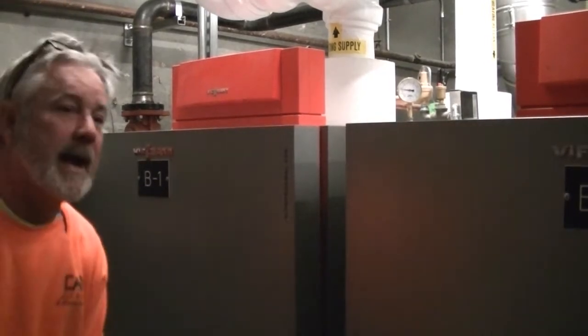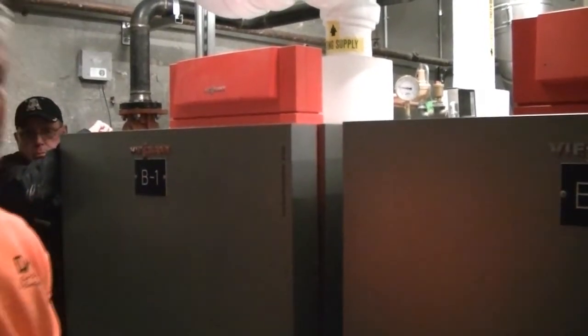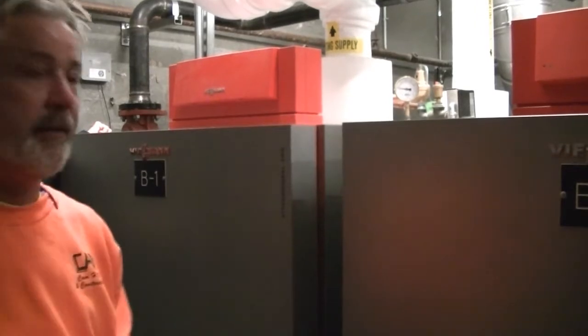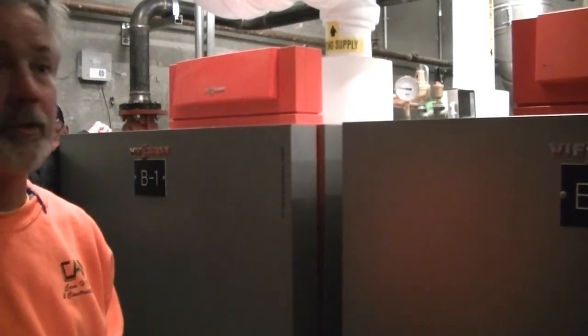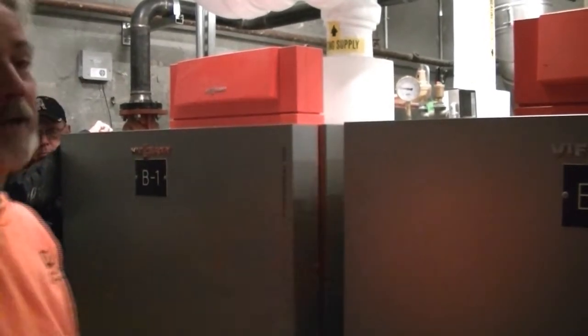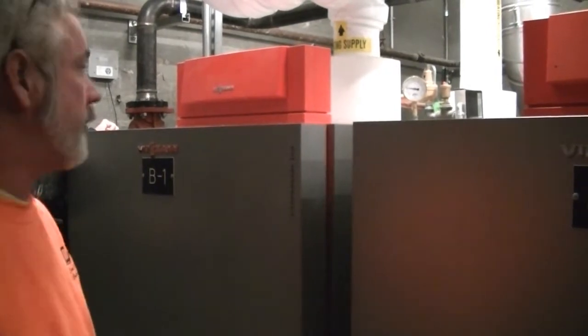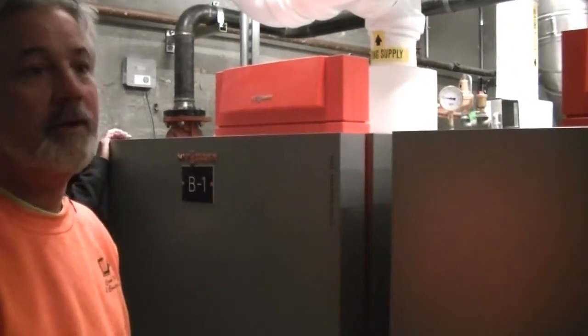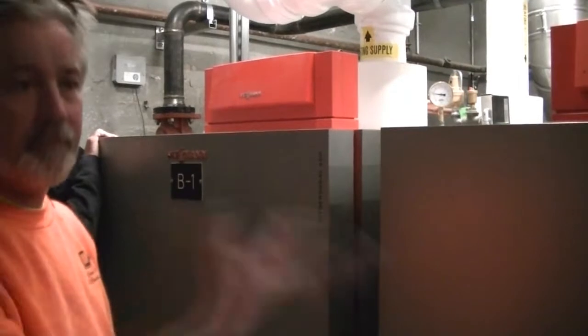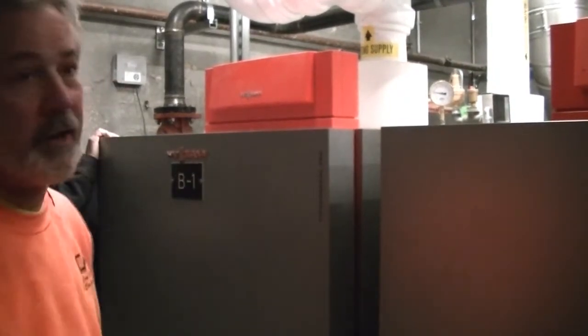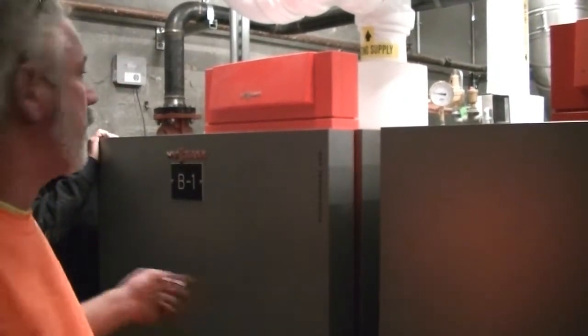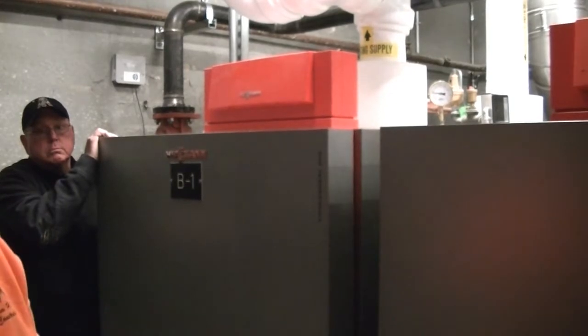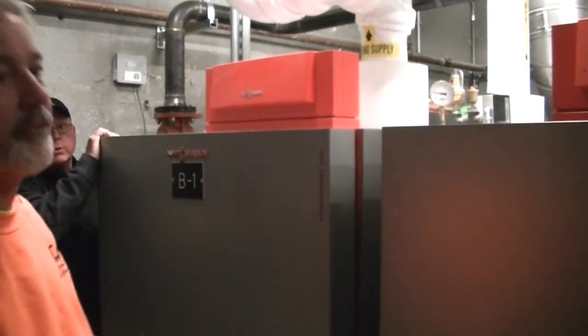So things like that, where the utility company's working outside and they interrupted the building power and tripped all the high limits because the boilers were in high fire when they shut the power off. So temperature went up, limits opened up, they didn't reset on their own. These boilers all have resettable high limits, okay? If not, they can be done through the front display.